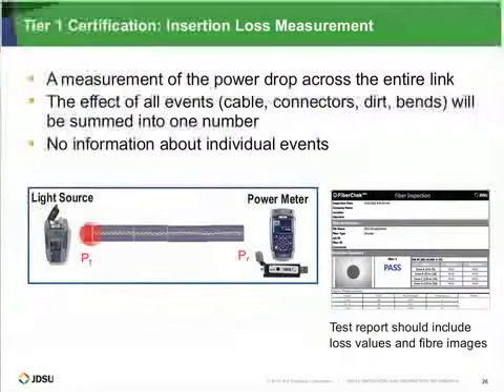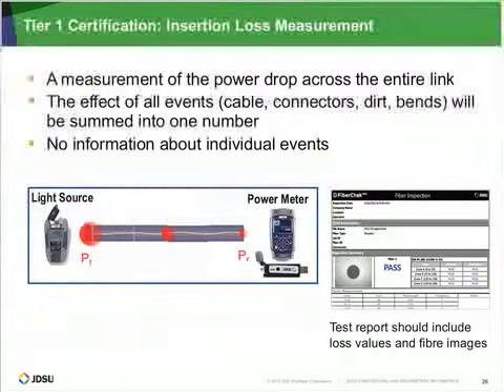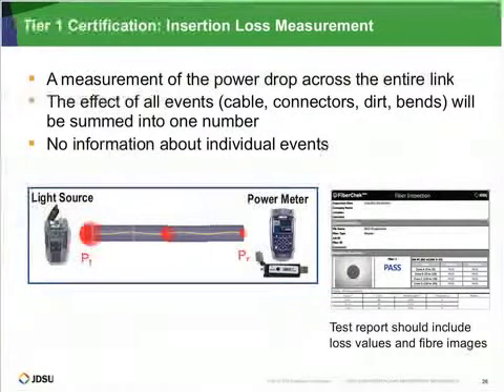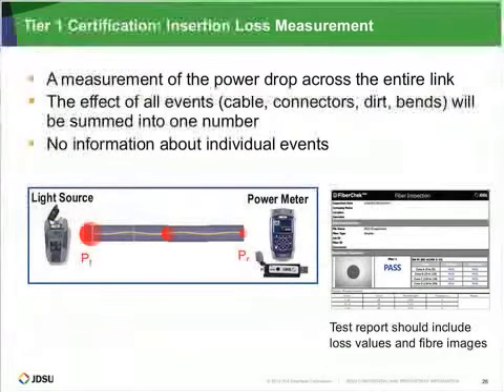So one of the most important things at the bottom, once you've done the fiber connector certification, is the insertion loss measurement. So this is purely a measurement of the power drop across the entire link. Typically this will be done on a fiber pair, so the loopback will be installed at the top of the fiber pair at the top of the tower. You'll have the source attached to one side of the link, and the power meter attached to the other side, and you'll measure the total loss of all the events, which includes the cable, the connectors, all the dirty connectors, all the bends. That'll be summed into a single number.